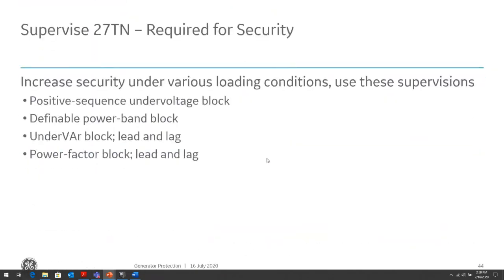Due to the complications, as I mentioned, with determining the third harmonic voltage, for certain operating conditions we need to block the 27 elements. There might be certain operating conditions, power factor or reactive operating conditions, where the third harmonic voltage might be insignificant. And even though the generator doesn't have a fault, the third harmonic voltage could drop based on that condition. So we might need to add conditions where, depending on the operating condition of the generator, we need to block that 27TN. During that time, when it's operating in that condition, we will lose that 15% coverage in the remaining part of the winding that is not covered by the 59N.